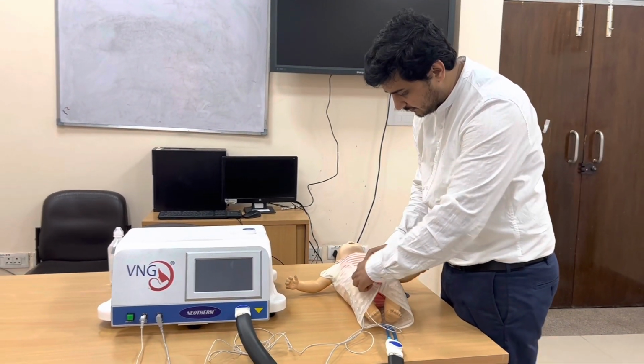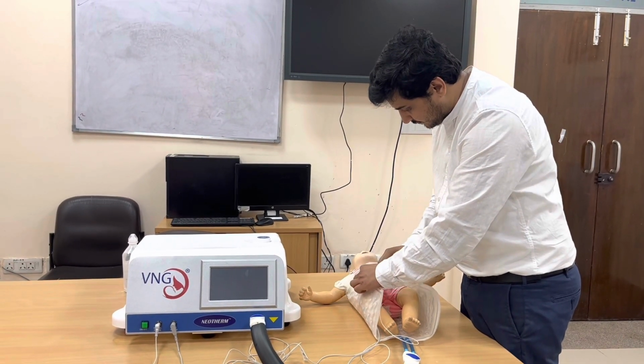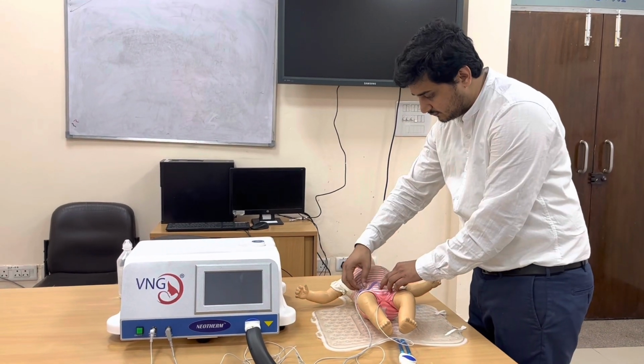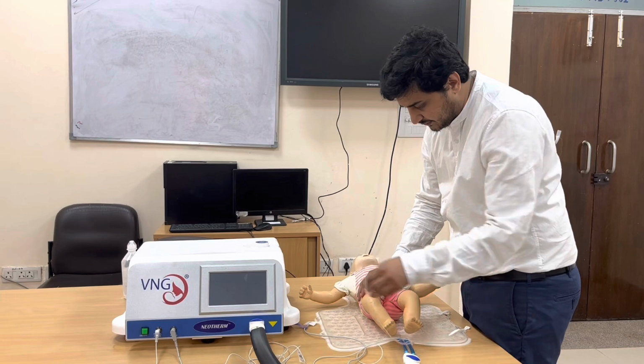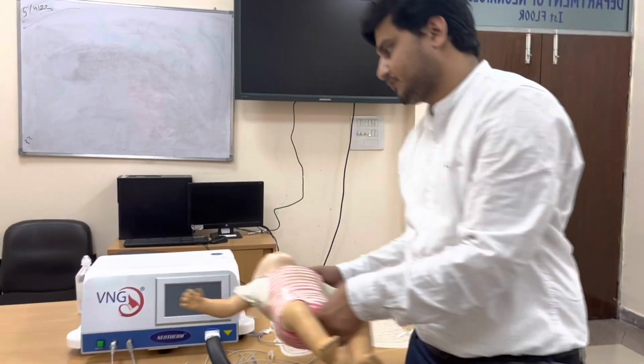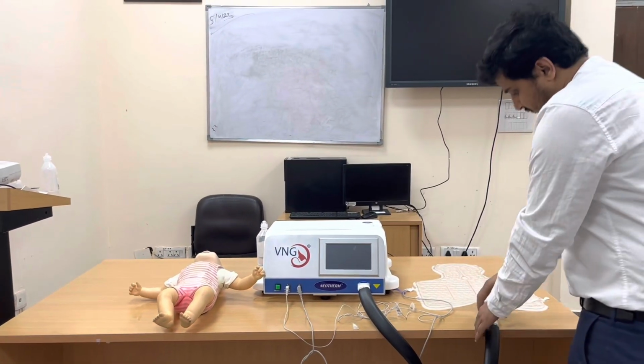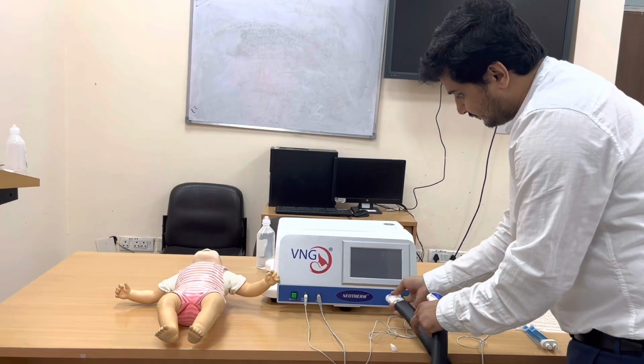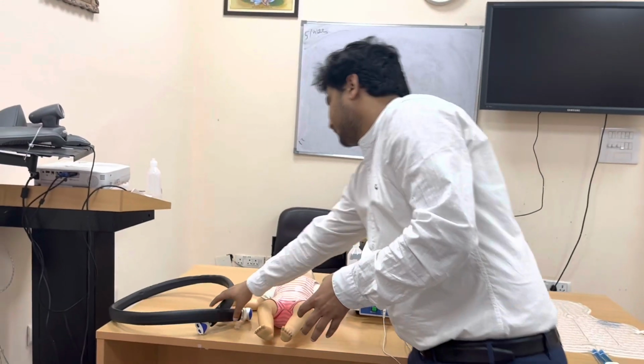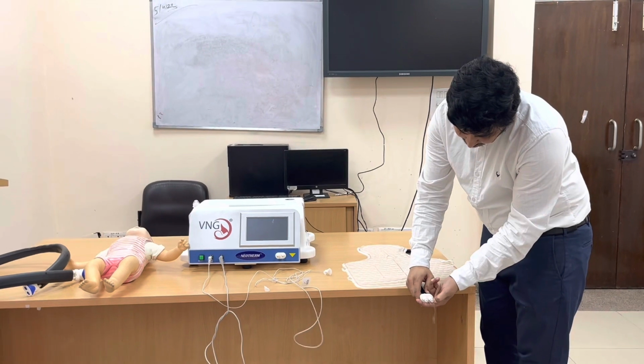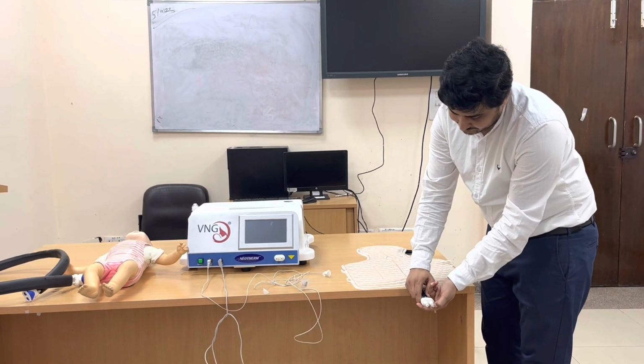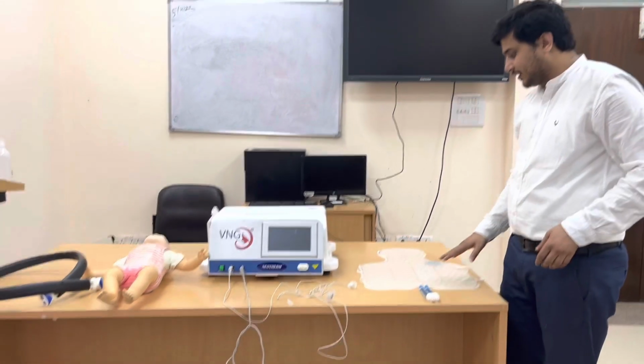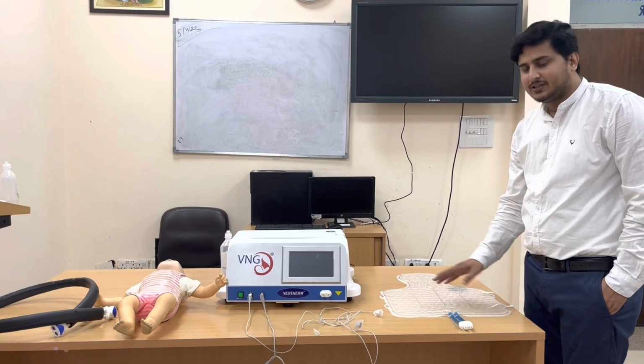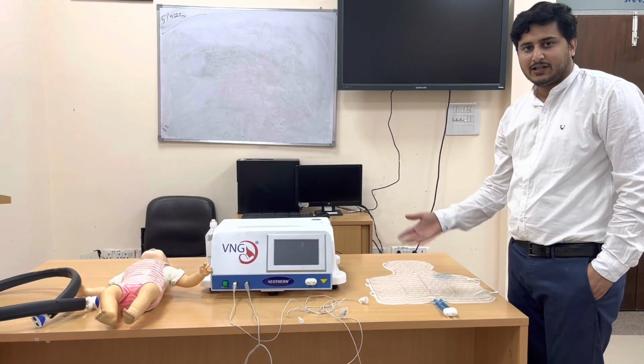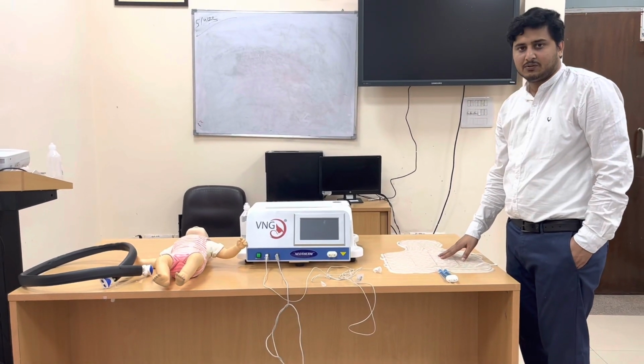untie the wraps, disconnect all the temperature probes. The coolant from the mattress can be removed by pressing the nozzle which is provided at the tube end in this fashion. So once we have disconnected and discarded all the remaining coolant from the mattress, you should sterilize it as per the antiseptic guidelines recommended by the manufacturer, and you have to terminate the therapy.